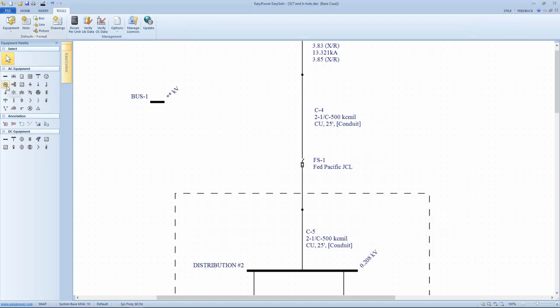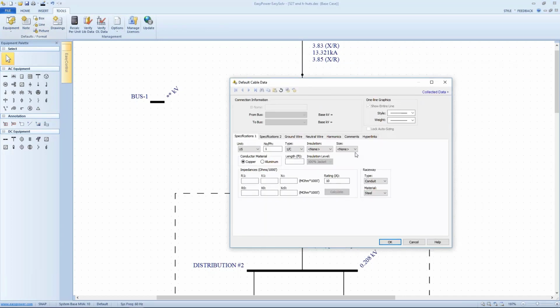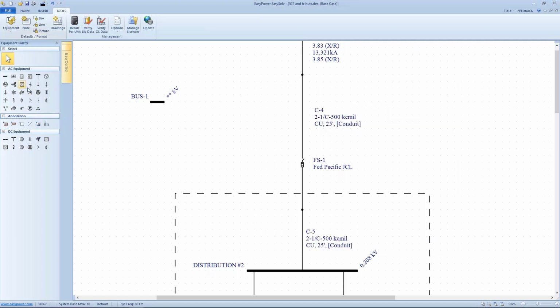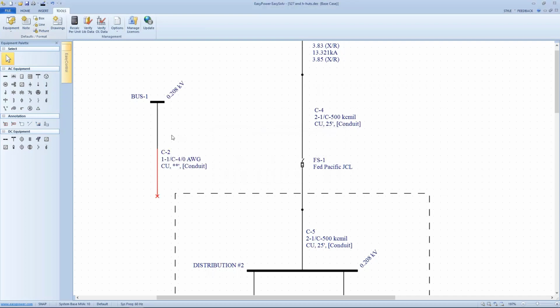Likewise, if we draw a cable, if I come back here to my cable rating, and let's say in my low voltage cables, most of the time I'm going to be using THHN, and let's say most of the buildings are wired with 4-aught. Then I can use this as my dimension, and it's copper, and we're routing it through steel conduit. By setting this up as my default, the next time I pick up the cable and put it in my one line, it'll be set up as a 4-aught copper through a steel conduit.